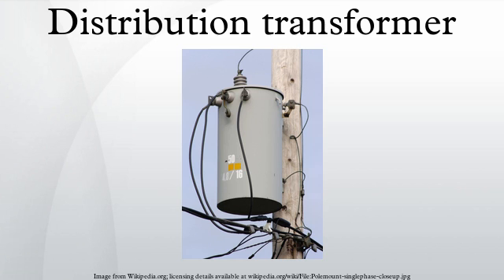Pole-mounted transformers often include accessories such as surge arresters or protective fuse links. A self-protected transformer includes an internal fuse and surge arrestor, while other transformers have these components mounted separately outside the tank. Pole-mounted transformers may have lugs allowing direct mounting to a pole, or may be mounted on cross-arms bolted to the pole. Aerial transformers larger than around 75 kVA may be mounted on a platform supported by two poles. A three-phase service may use three identical transformers, one per phase. Transformers designed for below-grade installation can be designed for periodic submersion in water.